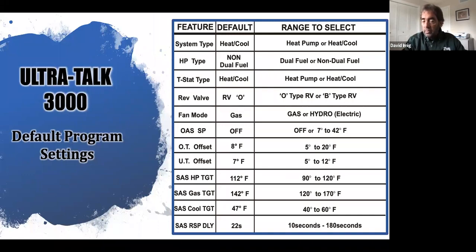So the OT offset is a high limit protection. We've selected 8 degrees higher than either one of my target temps, and it will cycle the equipment off. It's my high limit. I'm sensing too high heat, so I will cycle it off for a period of 3 minutes. At that time, I will make sure the temperatures are safe to operate again, and if there's still a heating call, I will bring that back on.